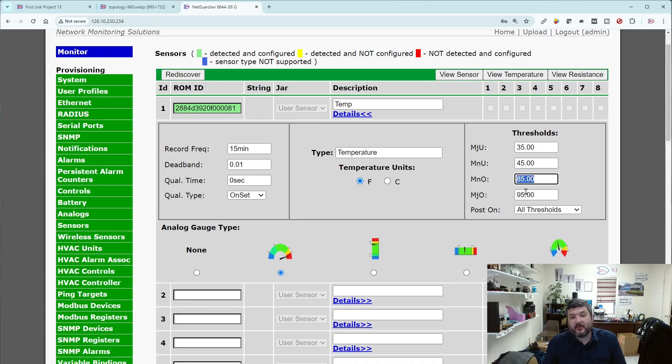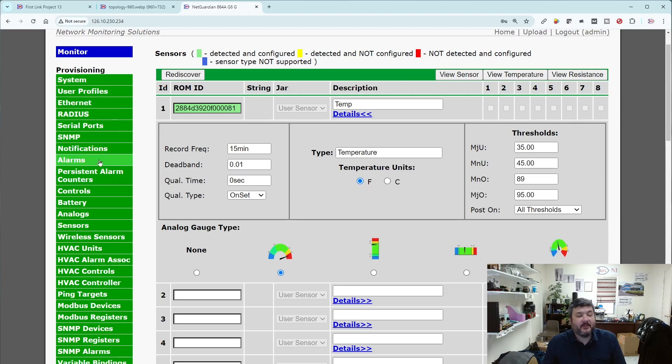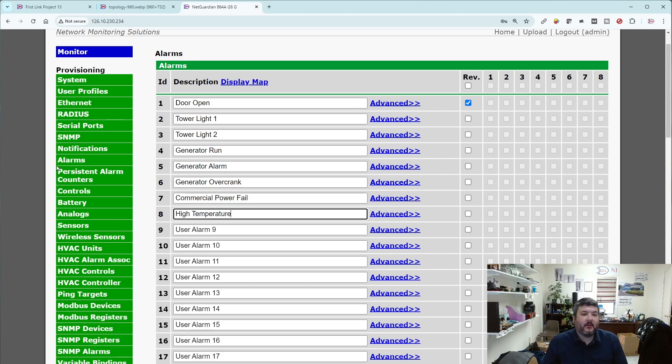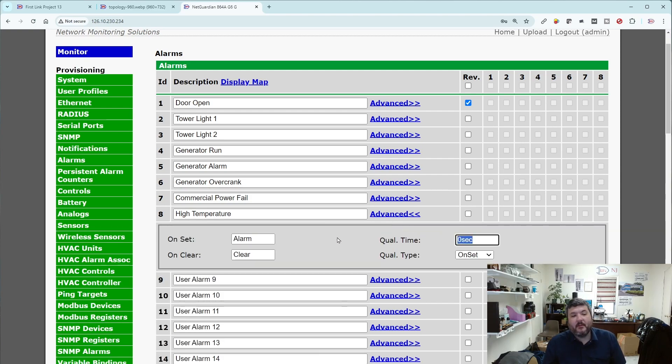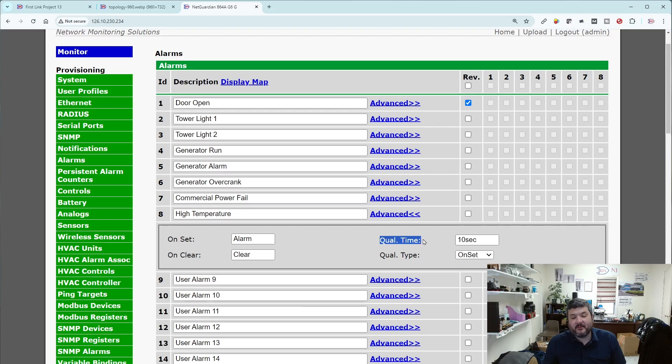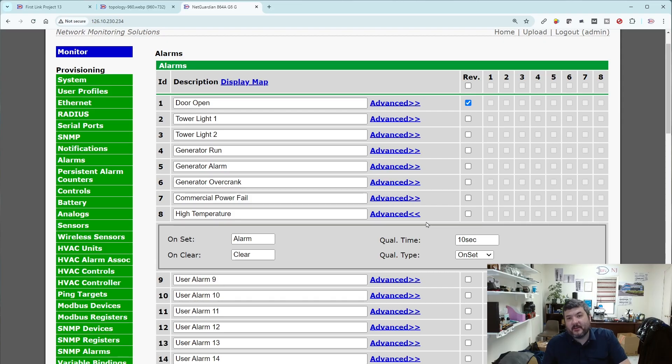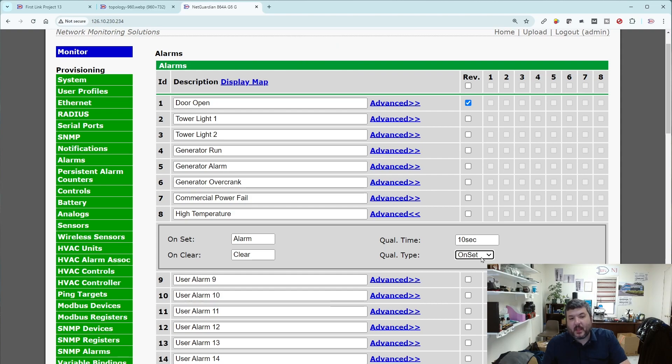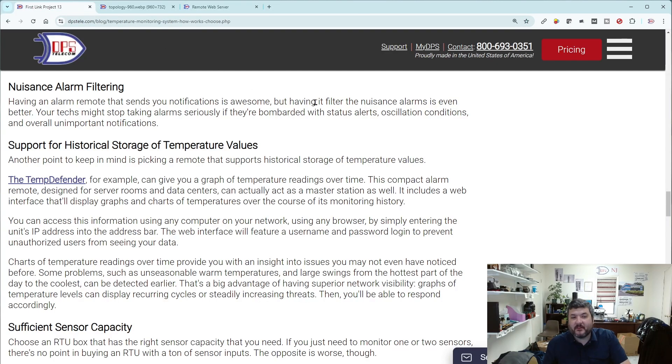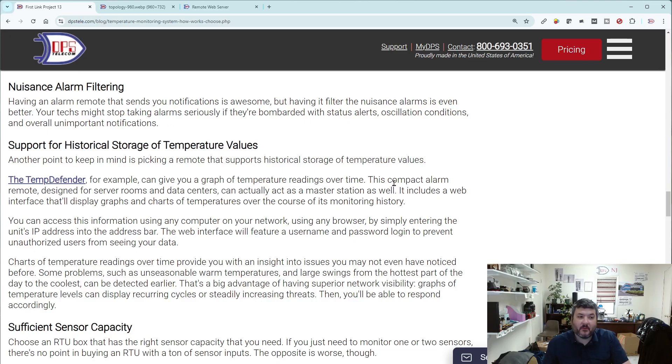On the discrete side, let's say I have a discrete temperature sensor. We'll call this high temperature. When this thing goes off, maybe it's a sensor that generally works pretty well, but it does flicker on and off for some weird reason. It has little hiccups where it momentarily latches and then unlatches within a few seconds. That's frustrating. What I could do is say give me 10 seconds here. That's a qualification timer. This is a function we build in our RTUs. You could say 'only tell me if the temperature is declared too high for at least 10 seconds straight.' I can set it just on set, so I don't have to worry about when it clears. That's a way to eliminate false alarms because every false alarm starts to train me and my team that I really don't need to look at the alarms. You do not want to do that.